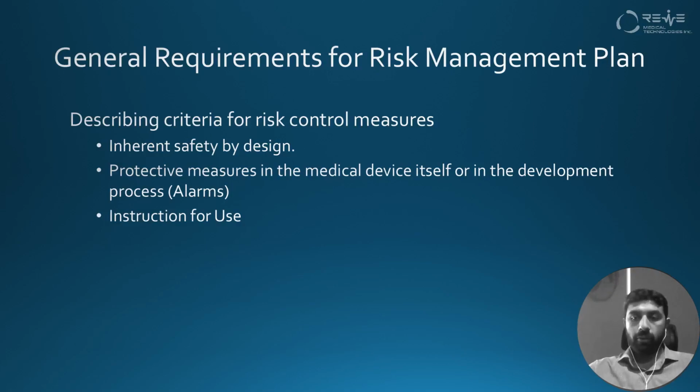Like, for example, we will introduce alarms in the medical device for those risks which we cannot control via design of the medical device. And then the third option is to mention that risk in the instructions for use of the device, or the operating manual of that device.